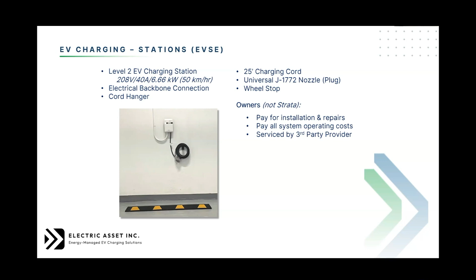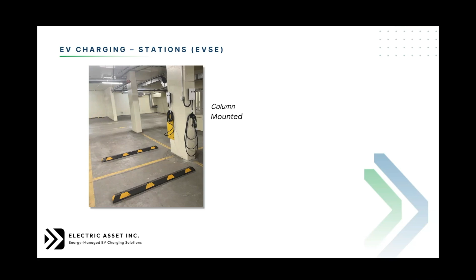If you don't have a suitable wall area that can be mounted, and if there's a column available in your parking stall at the front or nose end, the charger can be mounted on the column. If your parking stall doesn't have a suitable column, we can install what's called an EV pillar, a metal divider. Basically it's a metal wall that the charging station hangs on. Wires are contained inside the sheeting of the metal, and it can support a charger on both sides, so both owners on each side of the pillar can enjoy a charger if they want one.